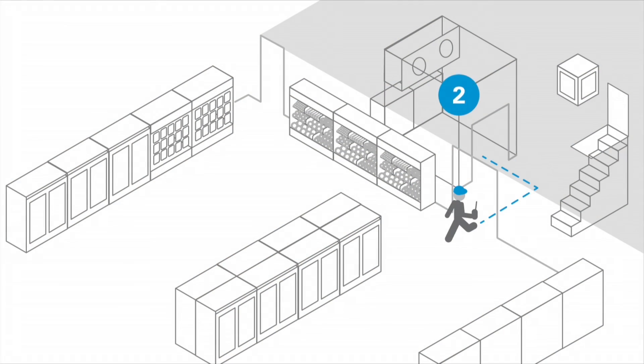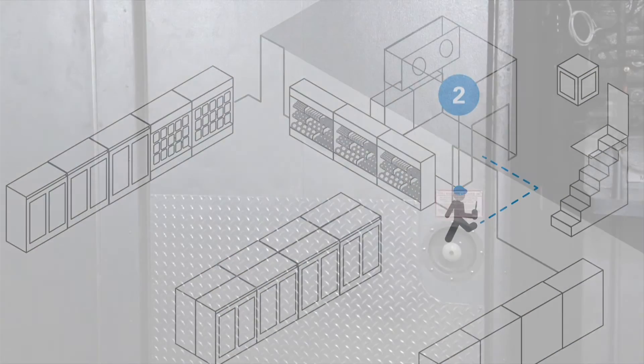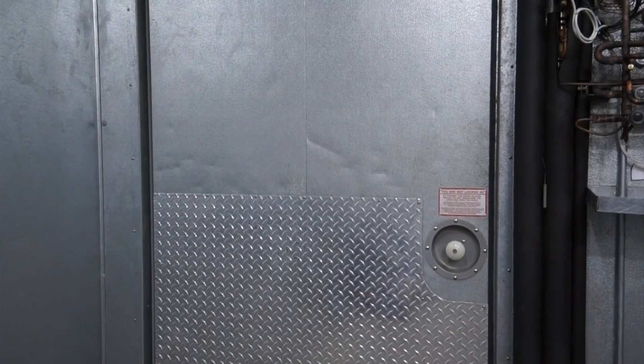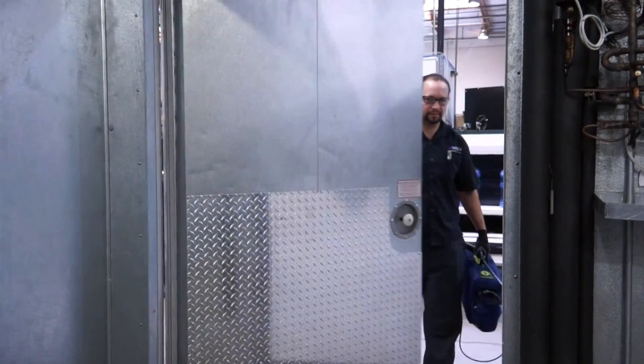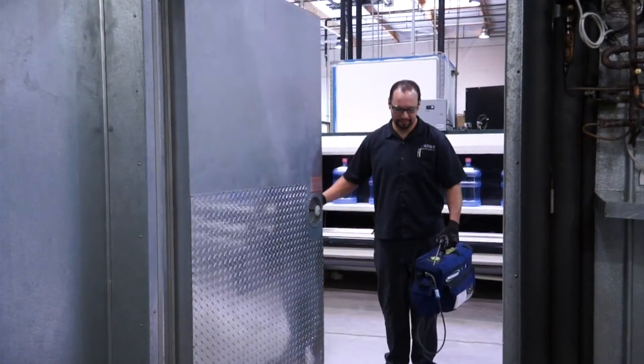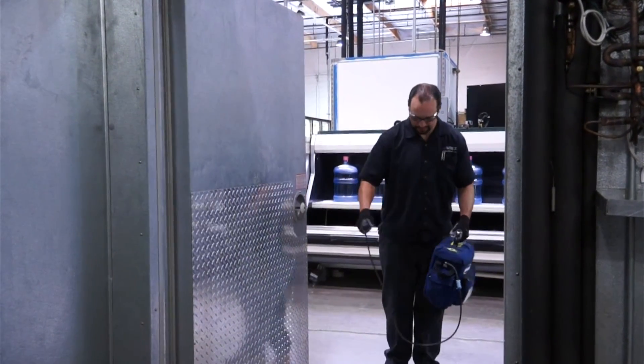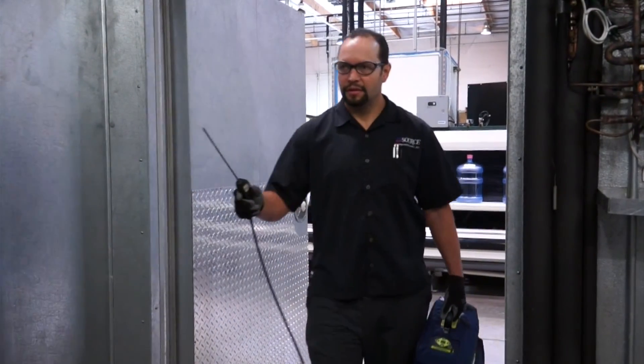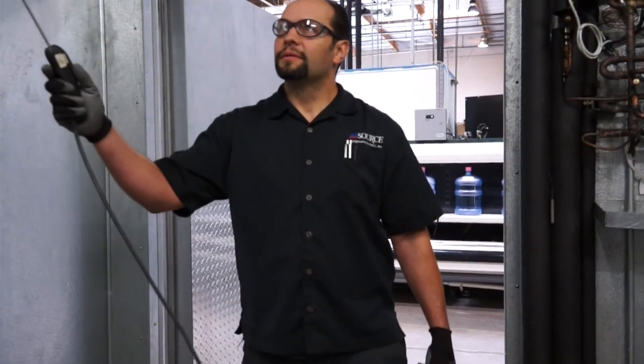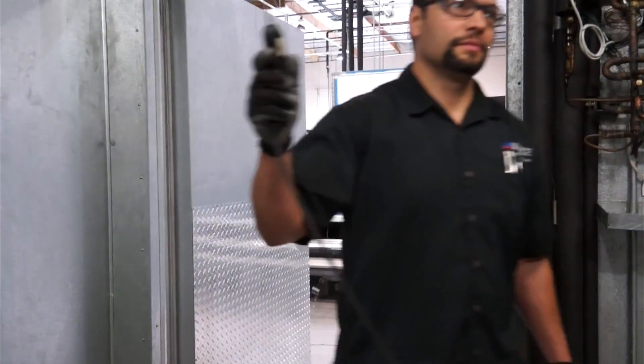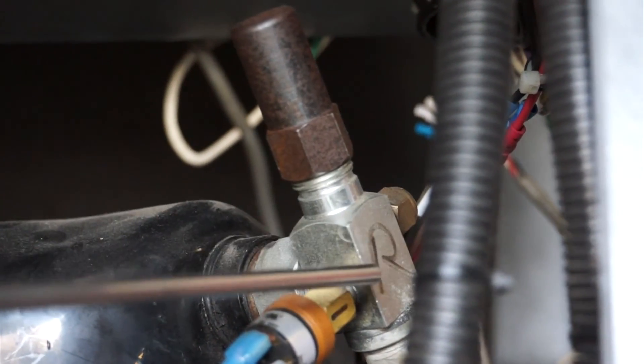Return to the walk-in area. A very large leak in the walk-in boxes will show up as soon as the door is opened, as refrigerant will saturate the atmosphere of the walk-in box. Check around the coil cabinet, around the expansion and isolation valves, and check pipe penetrations into the cooler or freezer.